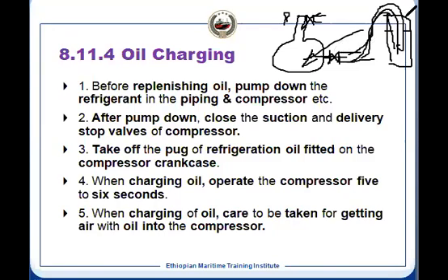The surface of the oil has atmospheric pressure on it, and this pressure is now sufficient to push the oil inside, because the inside pressure is lower than the atmospheric pressure. So this procedure is risky. There are chances of contamination. Air can enter, as it is an open container, because you have to have an open container so that atmospheric pressure is on the surface of the oil. Otherwise, it will not enter into the crankcase.